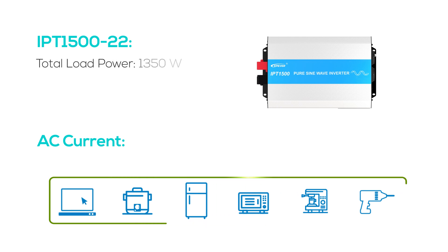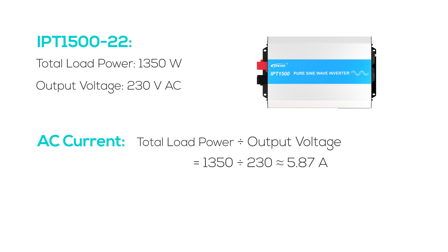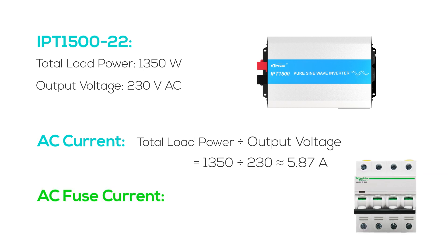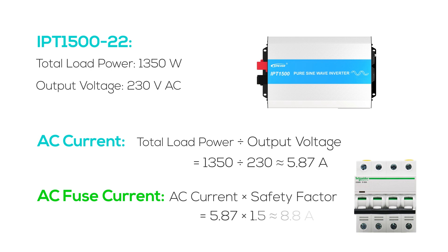The resulting figure should be multiplied by a safety factor — typically 1.5 for copper — to account for slight overloads. For the AC current calculation: if total load consumption is 1350 watts and AC voltage is 230 volts, the AC current is 5.87 amperes — simply divide total load power by output voltage. For the AC fuse, we recommend one that can handle 8.8 amperes, which is 1.5 times the AC current of 5.87 amperes.